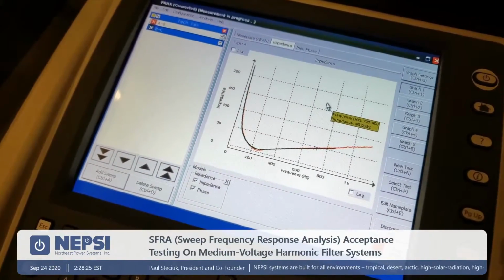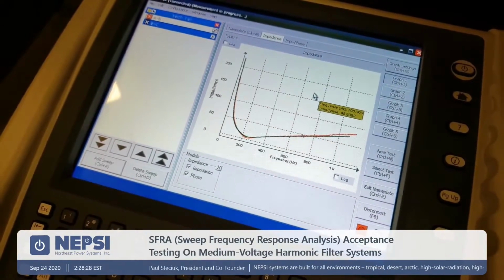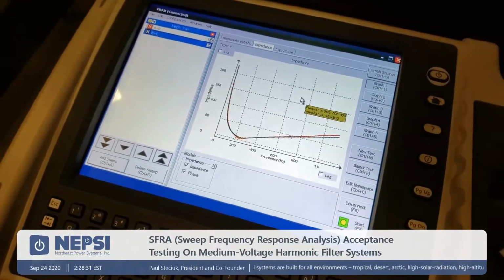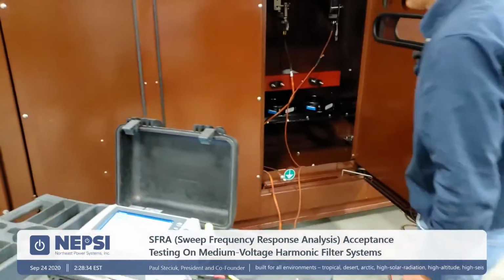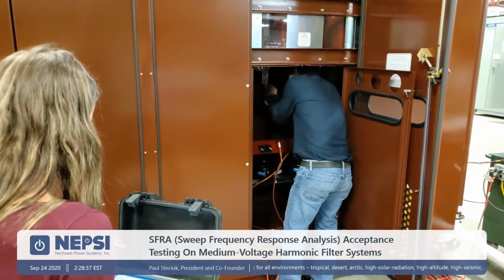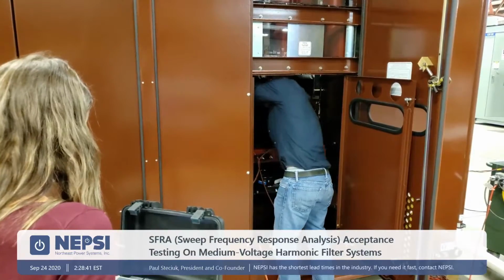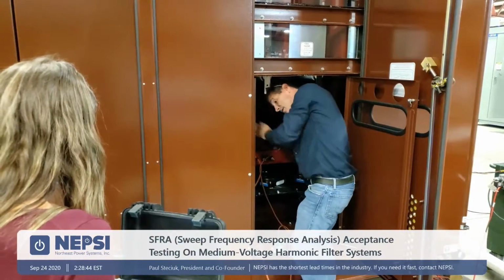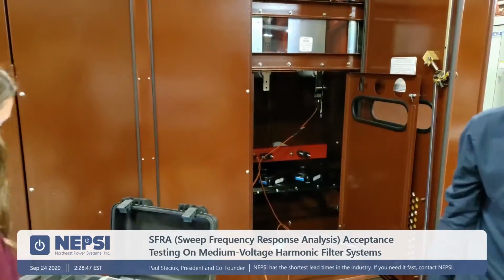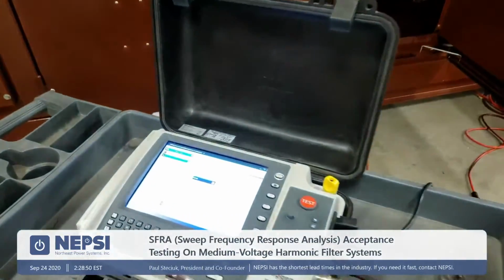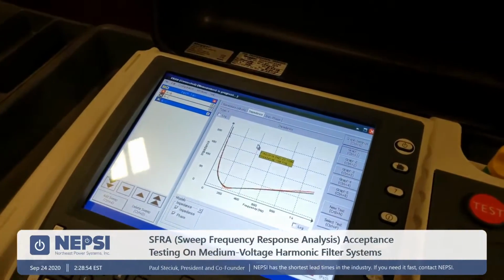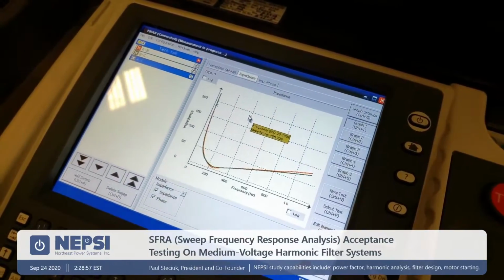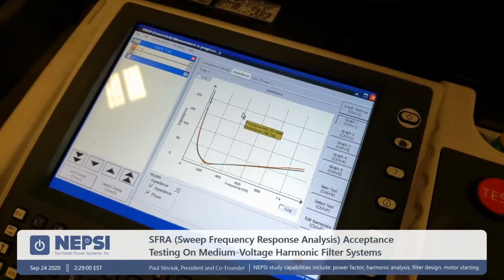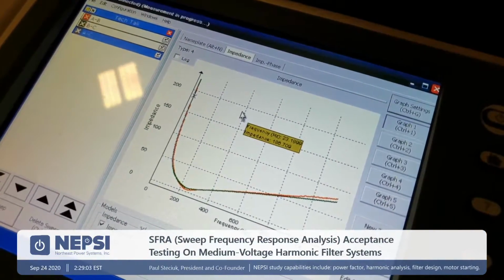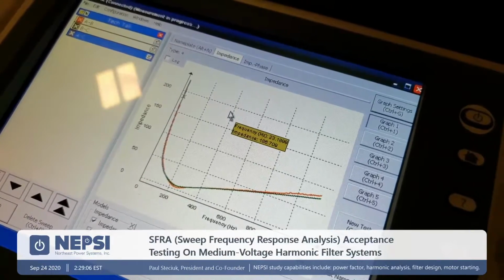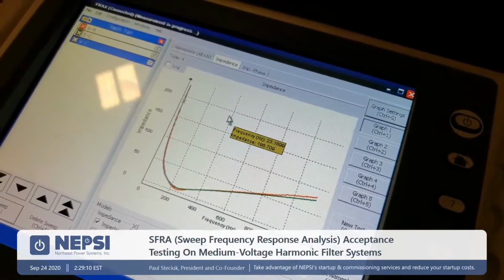And I'd like to perform a fourth test just so we can show that simulation. So now phase A to phase C is the last test to confirm the tuning point of all three phases. All right, we're on A to C. So it's really a fast test. It looks like we can get this done in just 10 minutes or so. We've effectively tested the entire harmonic filter impedance profile, and we can confirm it. Once this is done, you push it into Excel or something, and you plot it against a theoretical. Yep. So a very fast process.